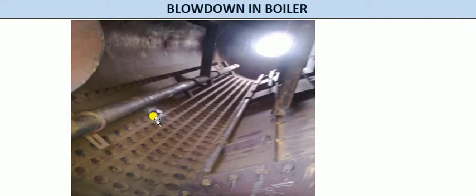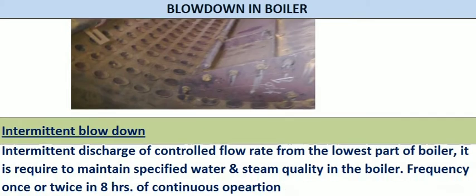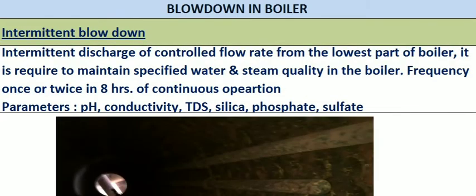There is also a plug for whenever the tubes get leaked during a hydro test — at that time we can plug it. Next is intermittent blowdown. Intermittent blowdown means that even after continuous blowdown operation, sometimes we are not able to sustain the required parameters — TDS, silica, phosphate, sulfate, or pH. When that happens, we want to bleed off a certain quantity of boiler water to sustain the water and steam quality. This is called intermittent blowdown.